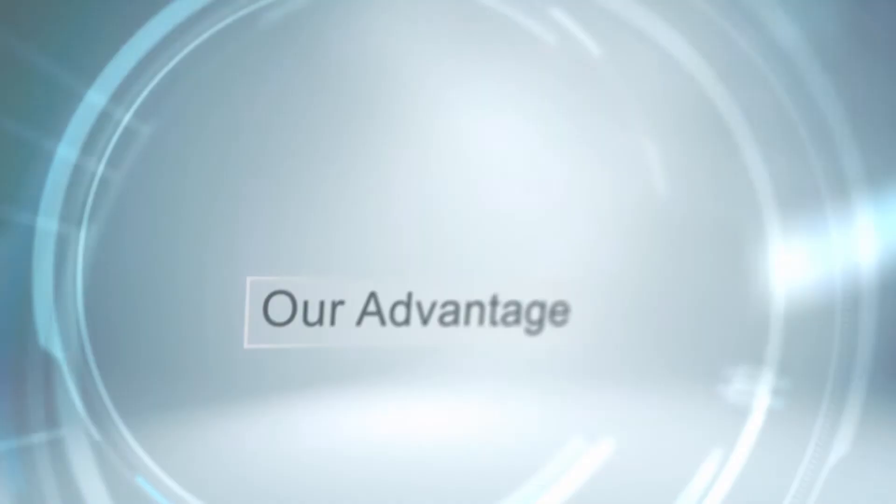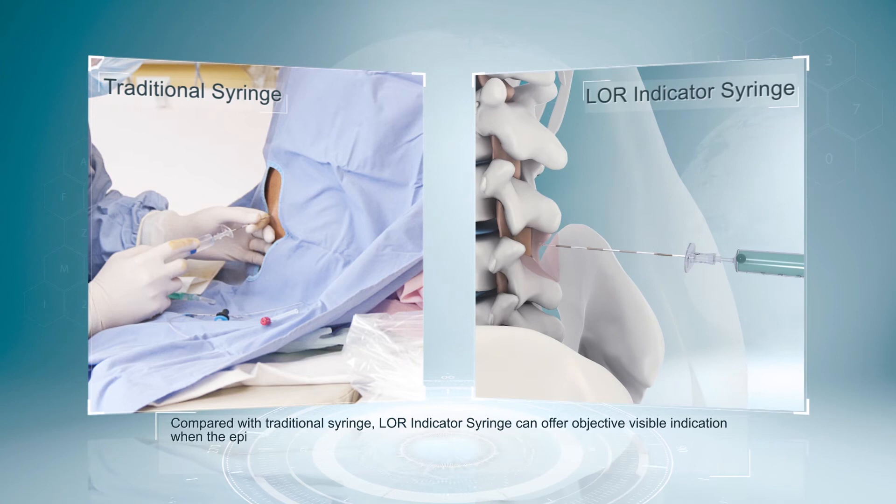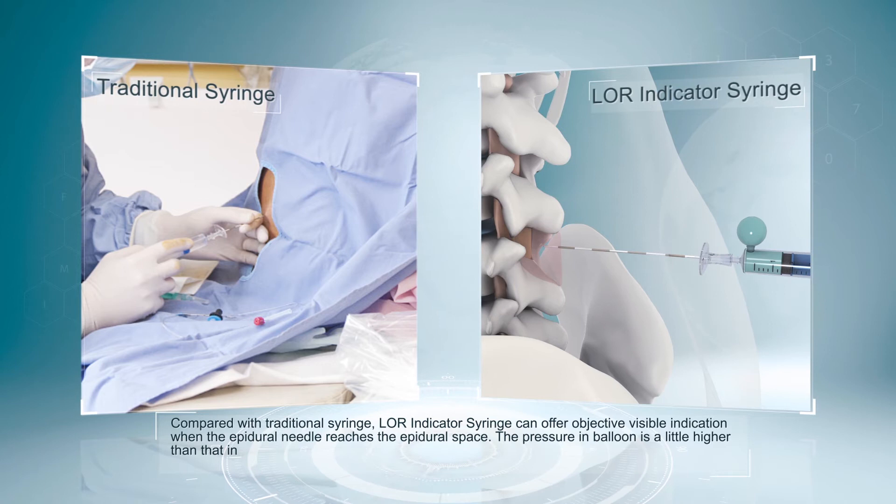Our advantage. Compared with the traditional syringe, the LOR Indicator Syringe can offer objective visible indication when the epidural needle reaches the epidural space. The pressure in the balloon is a little higher than that in the epidural space, so the balloon gets deflated promptly when the needle reaches the epidural space.